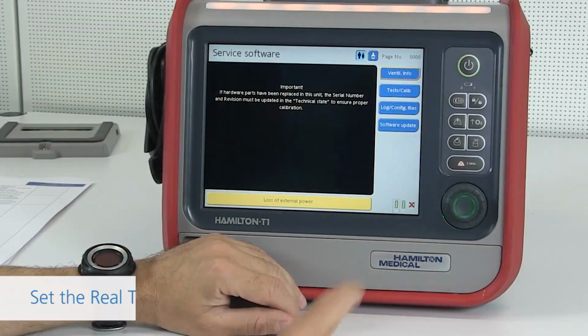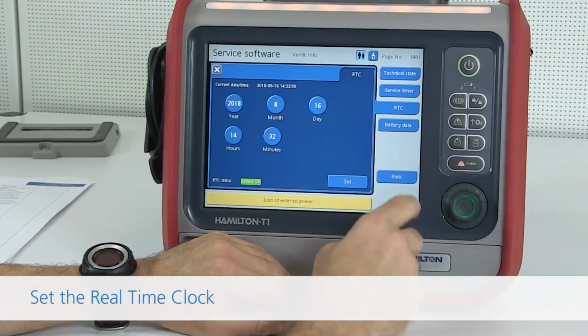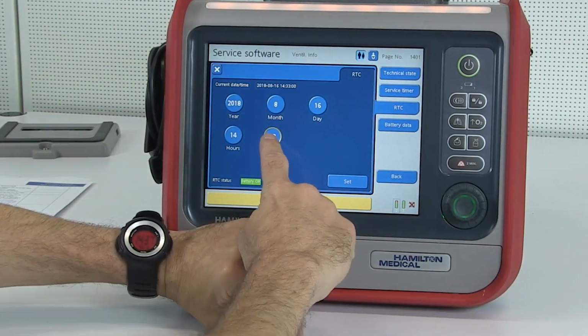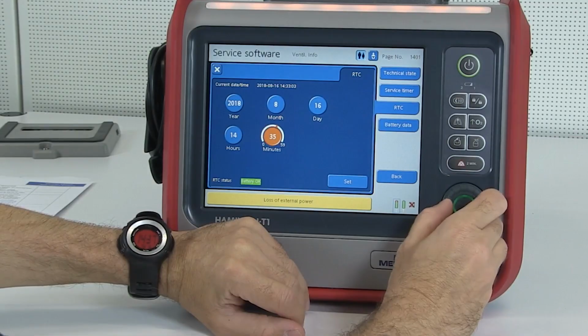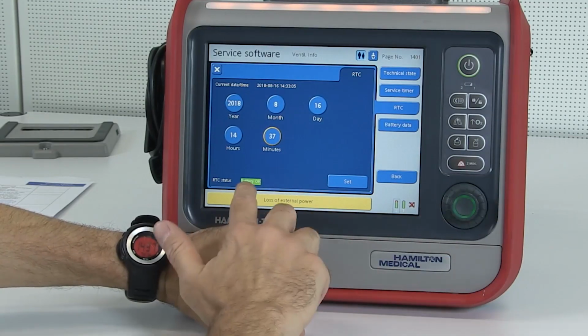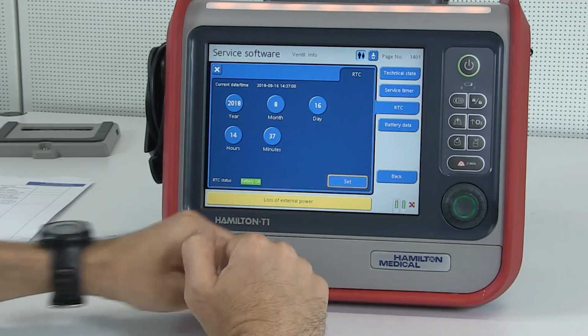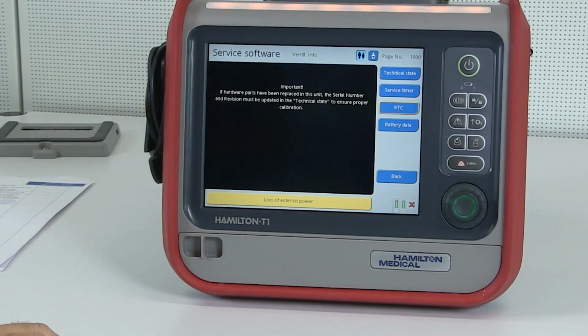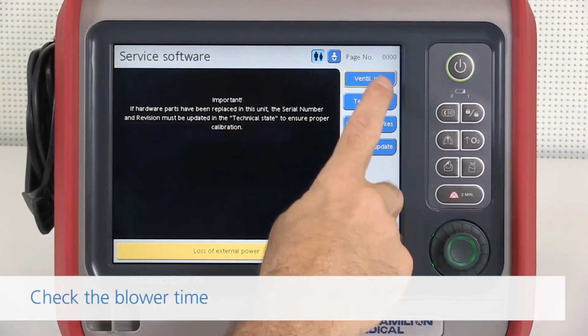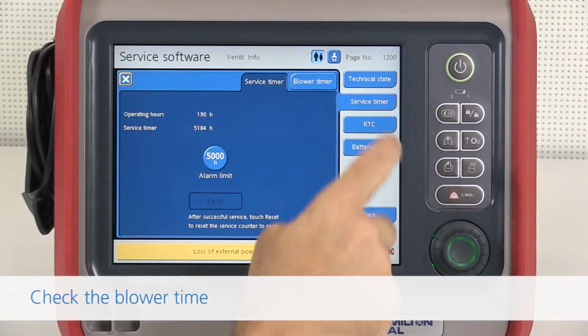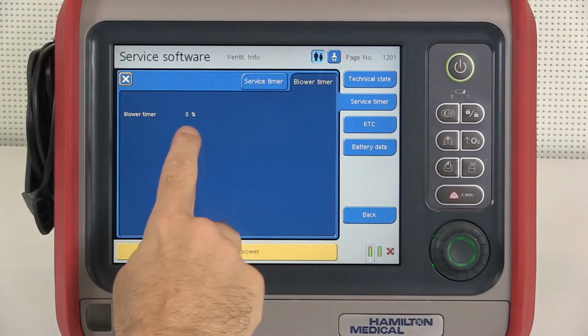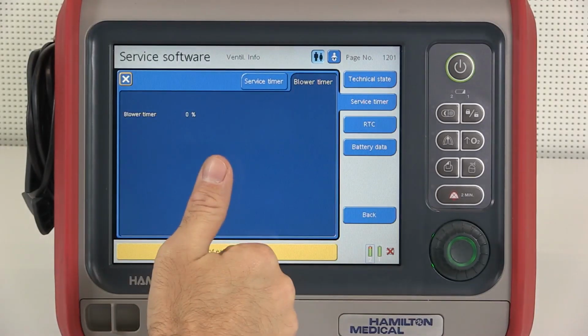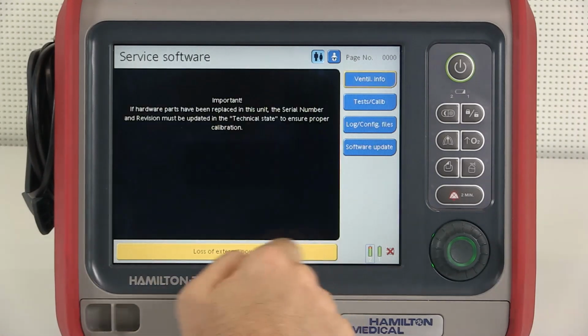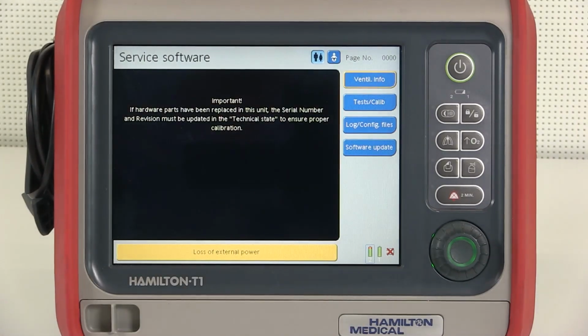In the main service software screen, touch Ventilator Info, then RTC. Confirm the real-time clock and adjust if necessary. At the same time, verify that the ventilator unit's internal RTC battery status shows battery OK, highlighted in green. In the main service software screen, touch Ventilator Info, Service Timer, and then Blower Timer. In this example, the blower is new. Replace the blower when the blower timer reaches 100% or is expected to reach 100% in 6 months' time.